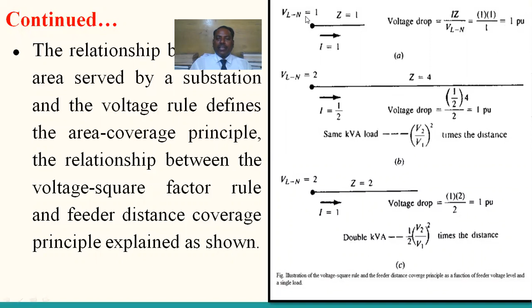So for the same KVA load, the distance is V2 by new voltage by old voltage whole square times the distance. And similarly, by keeping the same percentage voltage drop and double the voltage, the KVA load is to be double.